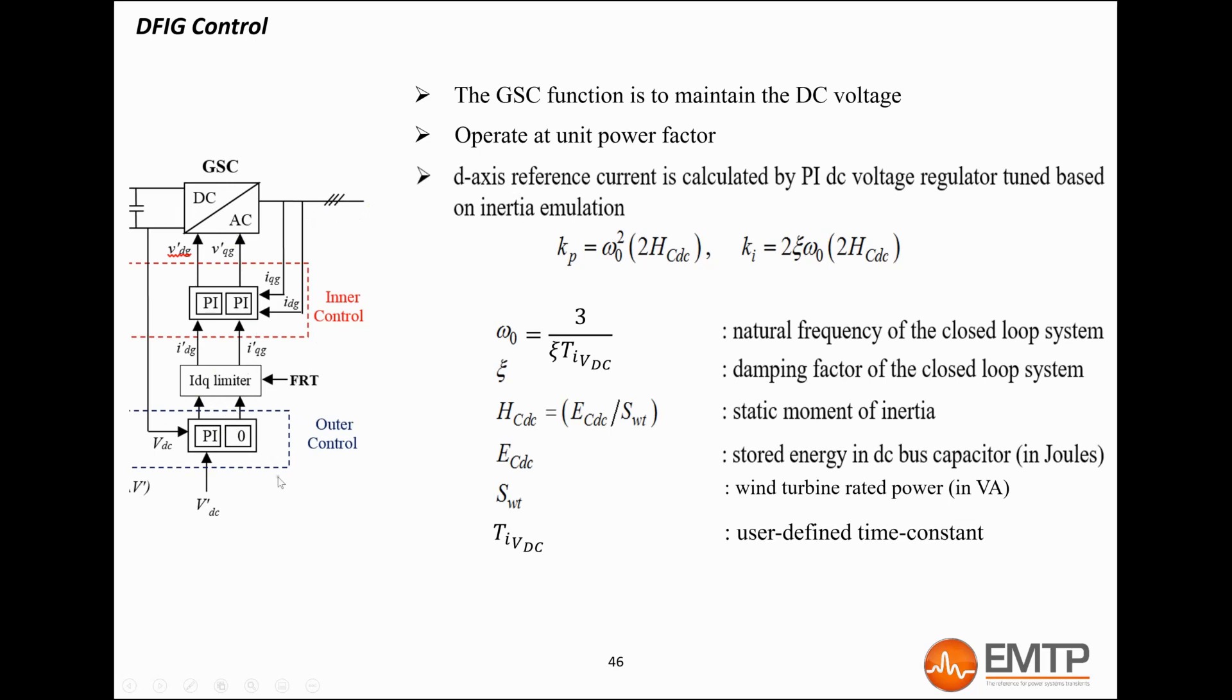Here again, two level control loops are utilized. On the d-axis, the outer loop regulates the DC bus voltage to its nominal value. The output of this loop is the d-axis current reference, which will be the reference for the inner loop. The inner loop, which is the fastest one, produces the d-axis voltage reference to follow the current reference.